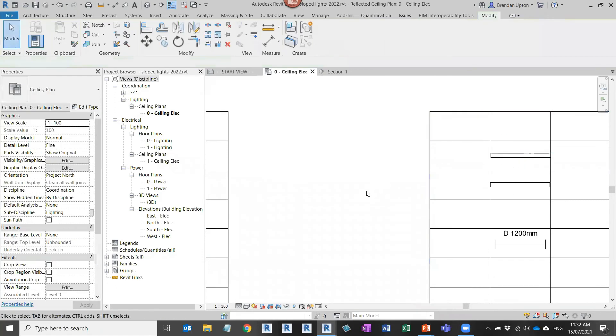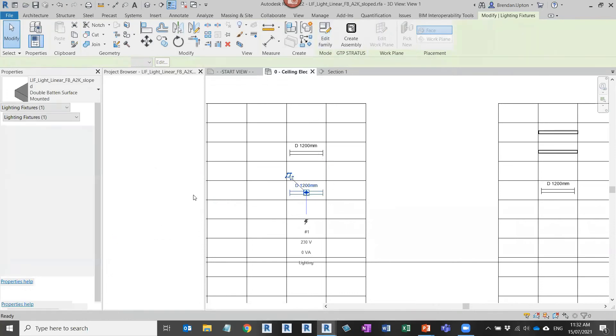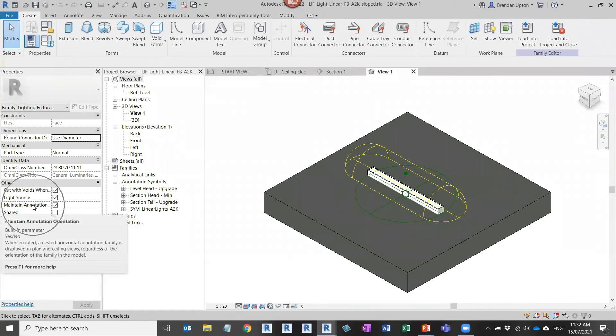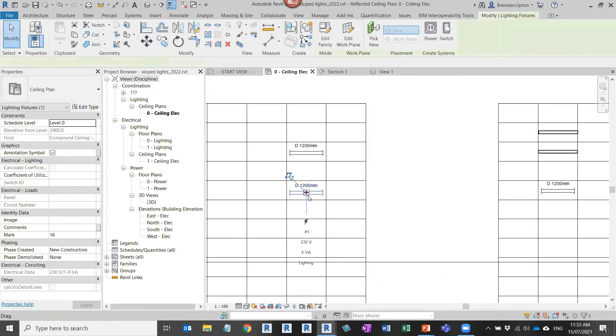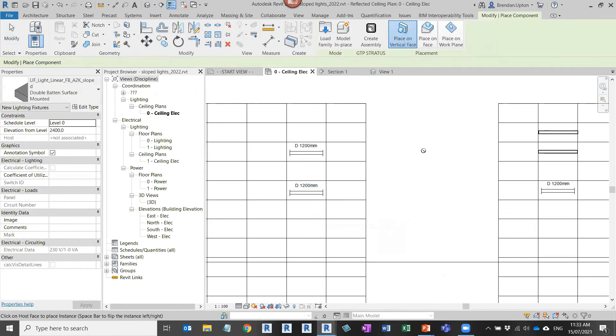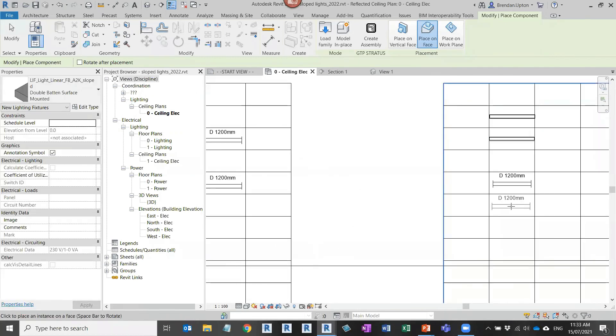What we can now do is edit the family and tick on the maintain annotation orientation setting. Back in the project I'll right-click and create similar, and you can see the symbol is now showing. There are a few gotchas to be aware of though. You do need to set up view templates with the correct detail level. I've set the 3D geometry to not be visible in fine mode — so your documentation views need to be set to the detail level where the 3D geometry is switched off, and then you'll get the symbol.